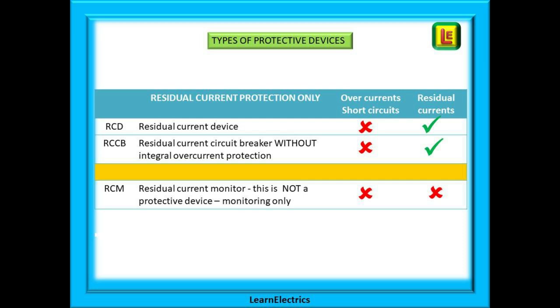Also shown on this chart is an RCM or residual current monitor. Please be very clear about this device. A residual current monitor is not an RCD. It offers no protection at all. All that an RCM does is to monitor residual currents and to warn the user if they exceed a certain level. A residual current monitor will not disconnect the circuit.